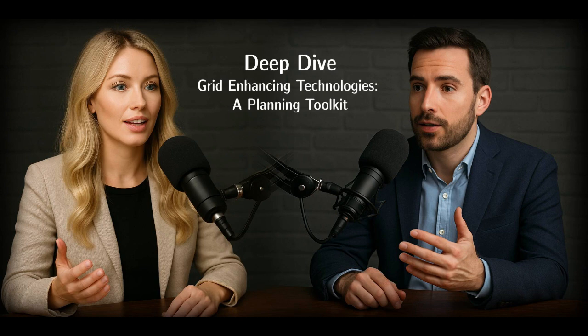Okay, so these sound like powerful tools, really fine-tuning the grid in ways we couldn't before. Are there simpler versions too? Yes, exactly. And that leads to smart wire technologies. Think of them as distributed FACTS or DFACTS. Distributed, meaning smaller units. Exactly. Modular power flow control devices. Maybe 1 to 50 megawatt capability per module. And the really neat thing is they can often be installed directly on existing transmission lines, sometimes without even needing an outage. Installed right on the line, wow.